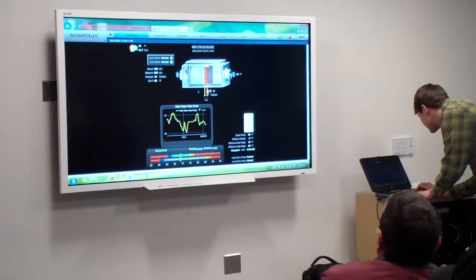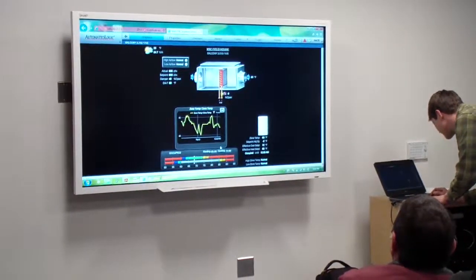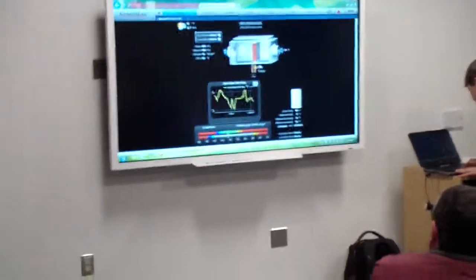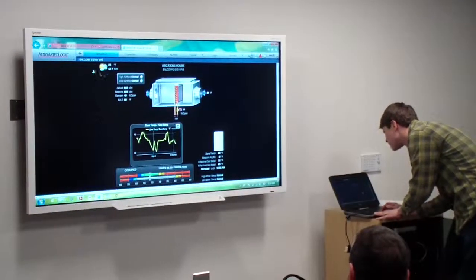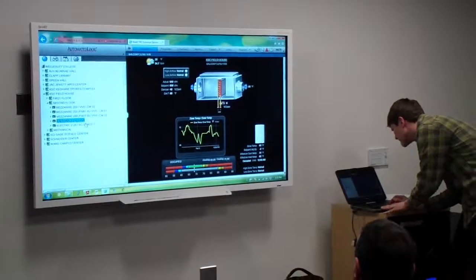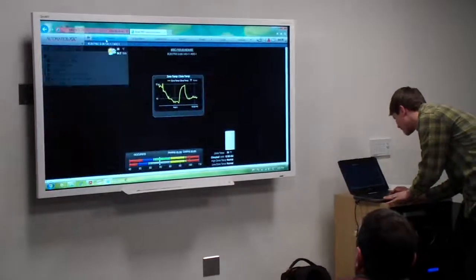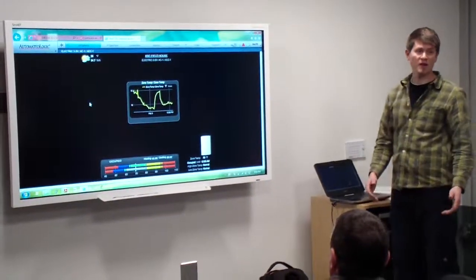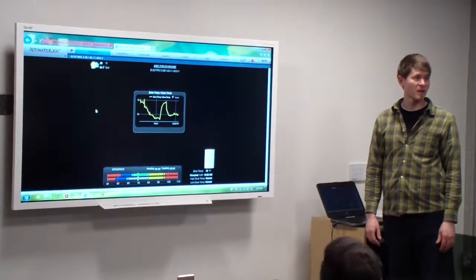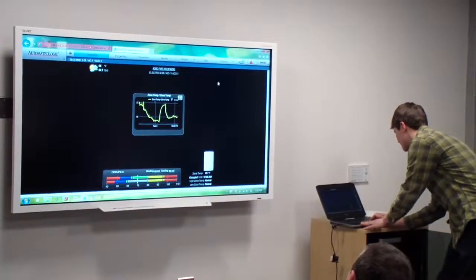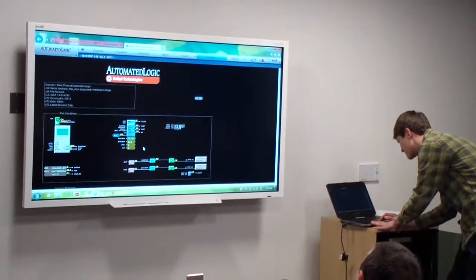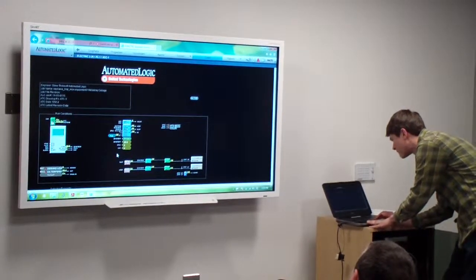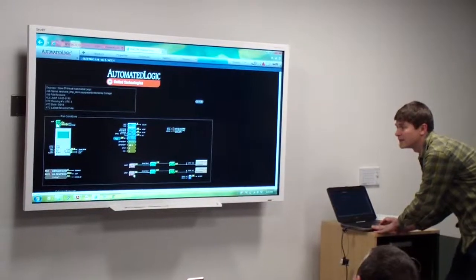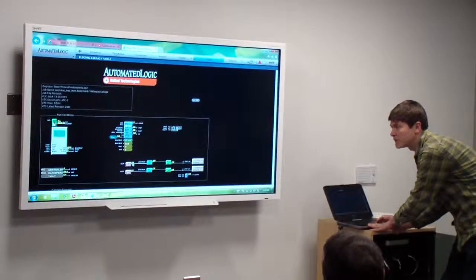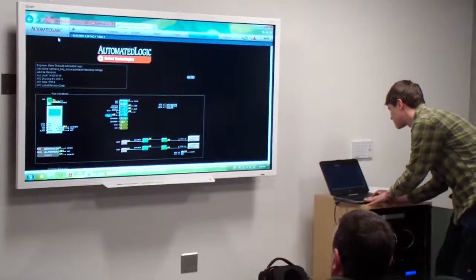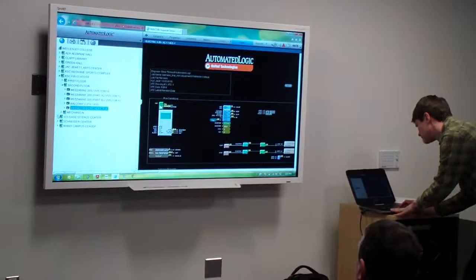We got the balcony section. Same thing, it's trying to go into cooling mode. You see that the reheat's closed. And then the electrical room, which is doing the same thing that we are in the mezzanine spaces. We're just monitoring the temperature inside the electrical room to pick up alarms. And I believe that the alarms are set up for the same plus or minus, yep, so plus or minus 5 degrees from the set point. So you've got 60 degrees is your low zone temp, and then 85 for your high zone temp.